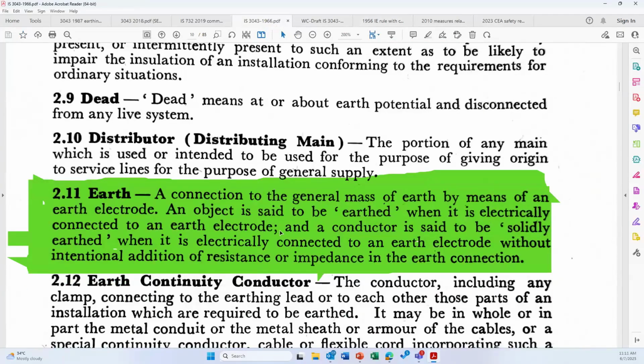Earth was defined as a connection to the general mass of Earth by means of an Earth electrode. So wherever we say Earth, this definition was giving an idea that you put an Earth electrode and connect to the Earth electrode. An object is said to be earthed when it is electrically connected to an earth electrode, and a conductor is said to be solidly earthed when it is electrically connected to an earth electrode without intentional addition of resistance or impedance in the earth connection. So basically, the definition was in a typical fashion in the 1966 IS 3043.